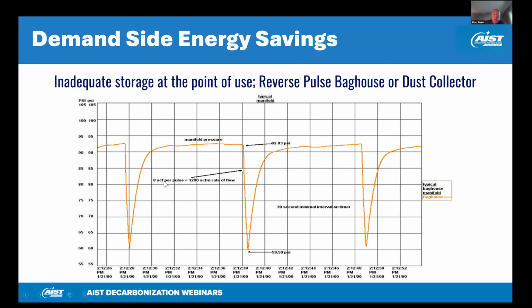When you measure this, it's only 8 cubic feet per pulse. However, due to how fast this rate of change is and the pulse duration, it creates a 1200 CFM rate of flow event. And that event affects the entire header. It causes that droop that I showed you in a previous slide. And once the system gets into that droop, it can't recover.